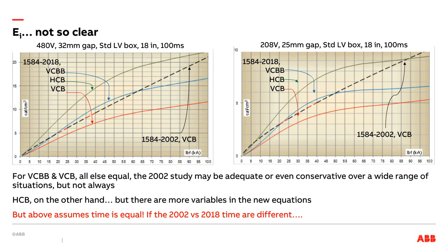Here you have 480 volts, 32 millimeter gap, standard box, 18 inches, 100 milliseconds clearing time, being fixed for all these conditions. And you look at the dashed line, which is a 2002 study. The color lines are a 2018 study. The VCB gives you less energy per any particular value of voltage fault current. That's a good thing. Means that the old study was conservative.